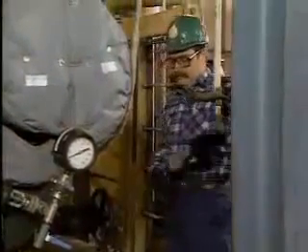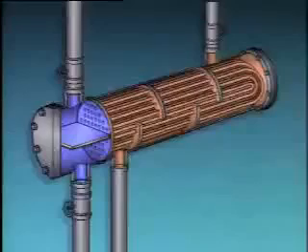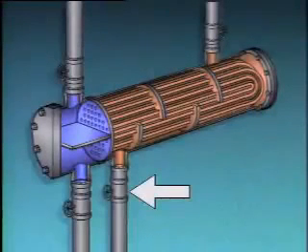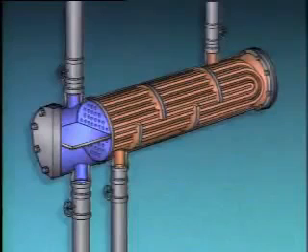At that point, he informs the control room that the shell side is lined up and that they can establish the proper flow rate through the shell. On the heat exchanger shown in this example, there is no isolation valve on the outlet of the shell side. Some shell and tube heat exchangers have an isolation valve on this outlet. With those heat exchangers, the isolation valve must be opened to complete the flow path through the unit.